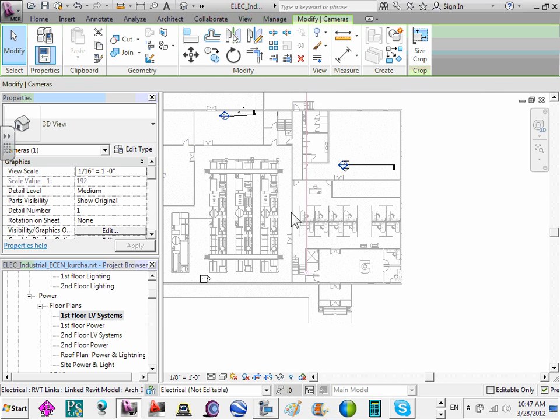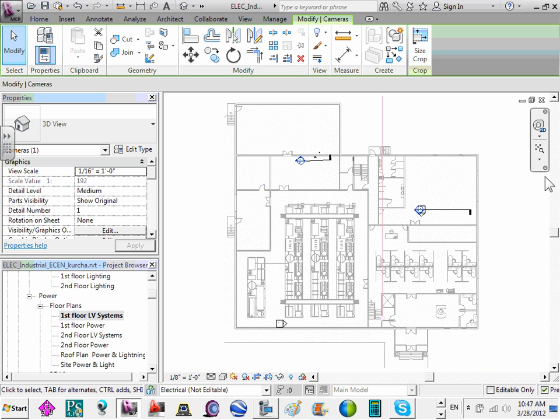The main control panel room and the electrical room is where you're going to have your main panel, and you're going to have a smoke detector above the panel. It used to be you had to have a smoke detector and a manual pull station. Manual pull stations are pretty much going away. They're just a nuisance for a lot of people to trip, and with the sensitivity of the detectors now and the technology they have, your smoke detector is going to go off most likely before a pull station.